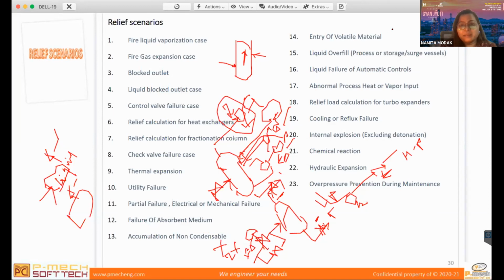Then entry of volatile material. So as I give you example of the fired heater. In a fired heater, normally you have a hot oil as a fluid, but sometimes this hot oil also gets condensed. So some water comes into it, or maybe contamination by some light oil, hydrocarbon of your plant. So what happens in this case, when that fluid enters this fired heater, along with your hot oil, basically water and light hydrocarbons have a tendency to vaporize first. So a lot of vapor gets generated. So that is this scenario.